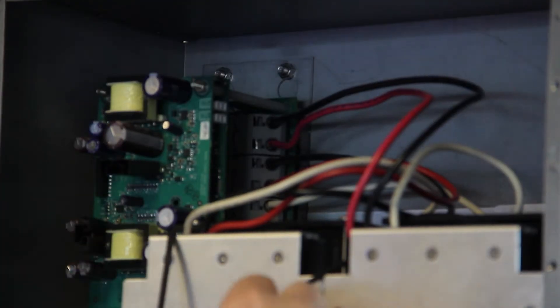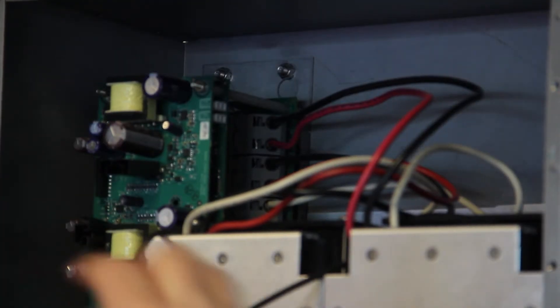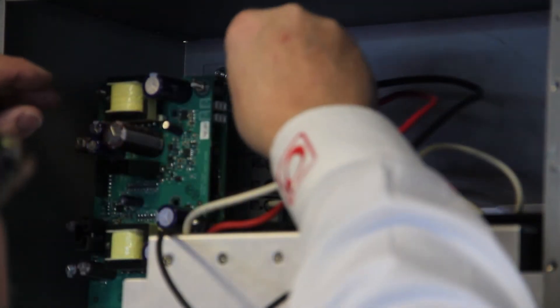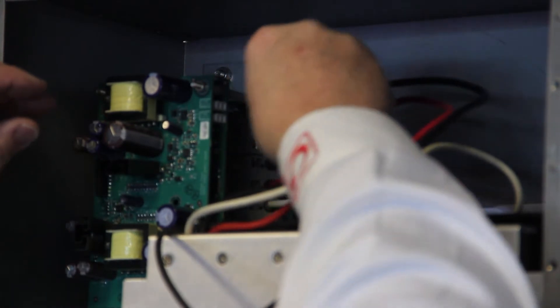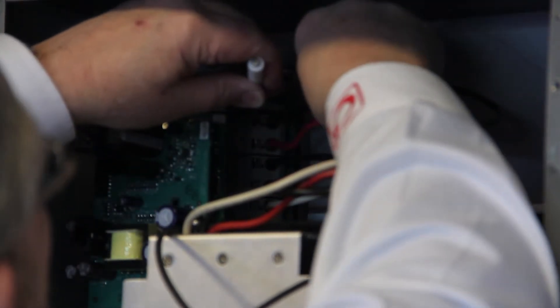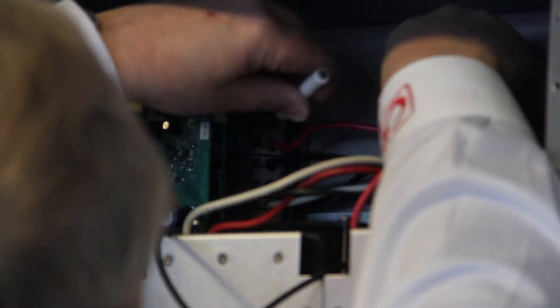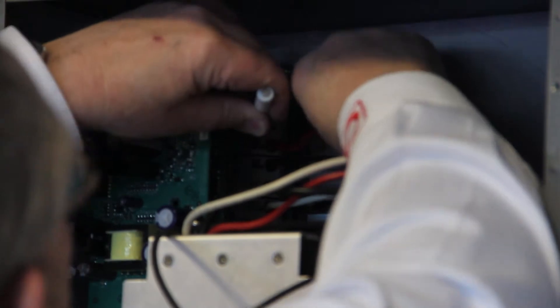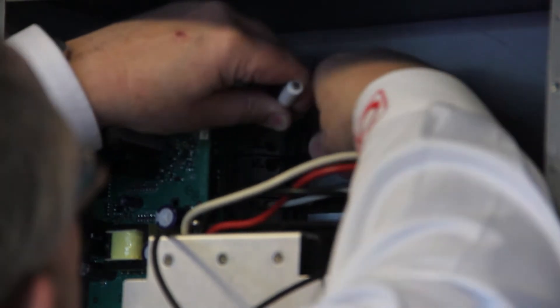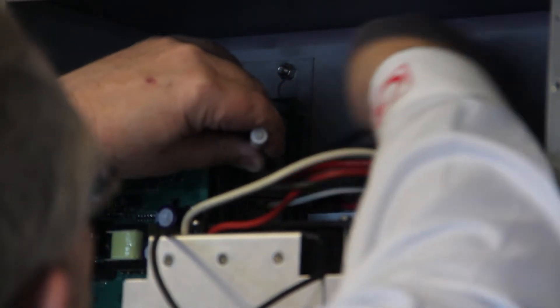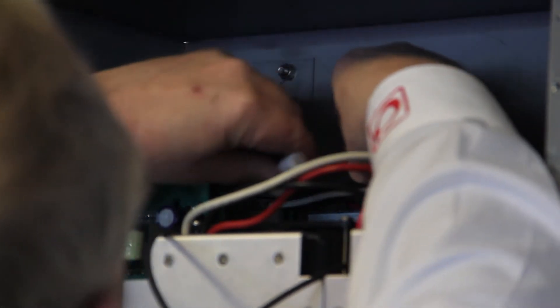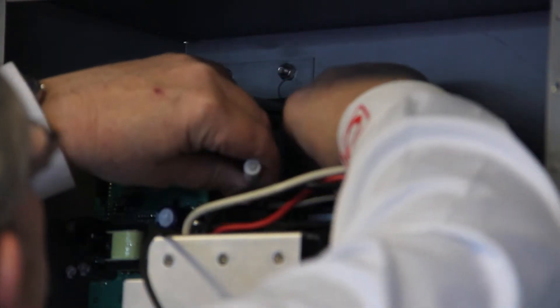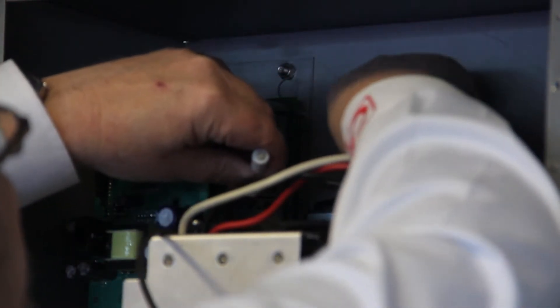Next, disconnect wires from the power module to the PCBA. Depending on the model, you may have six or four wires. You either need to unlock the tabs to pull the wires from the terminals or insert a flat screwdriver into the terminal block slot, then lever the screwdriver outwards to release the tension from each wire.